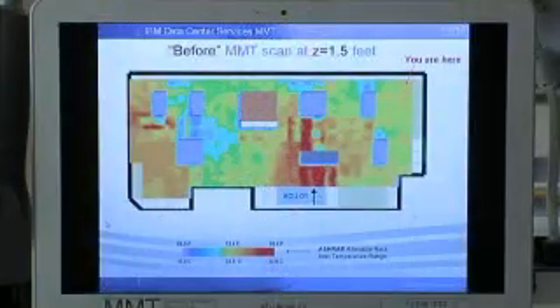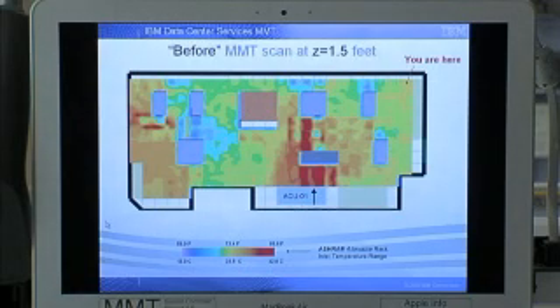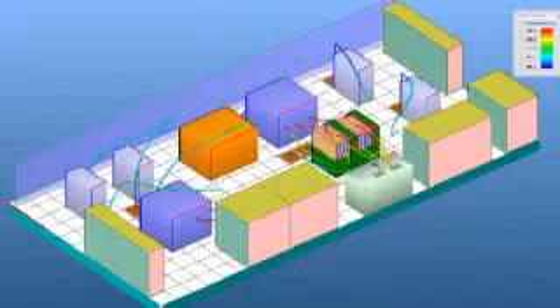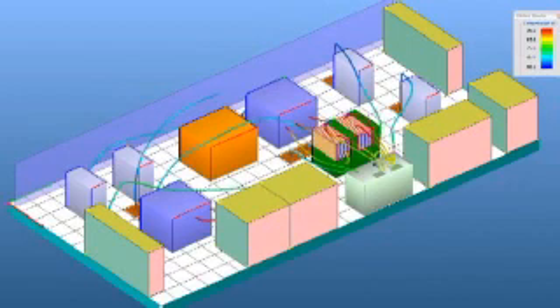We took the results of the MMT study and then looked at the data center and tried to determine where the problem areas were, where the high heat loads were, where the over temperature problems were, and then took those results and built on that using another tool called CFD, Computational Fluid Dynamics tool. So we ran about 40 odd runs of different layouts to try to optimize the data center from a ventilation standpoint, from a heat load standpoint. And from those results, we had an optimized data center, the most efficient, using the best practices that we could deploy in this data center.